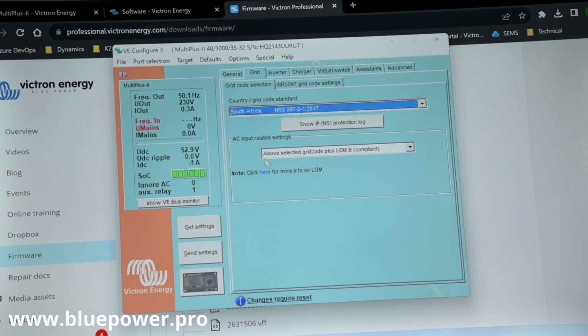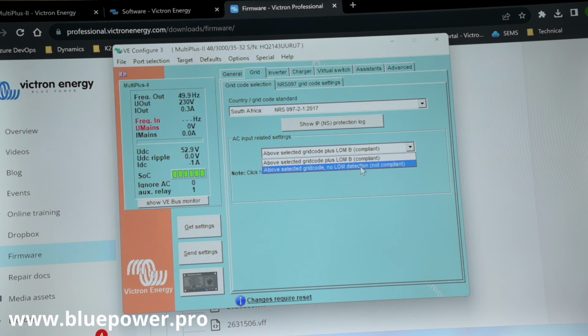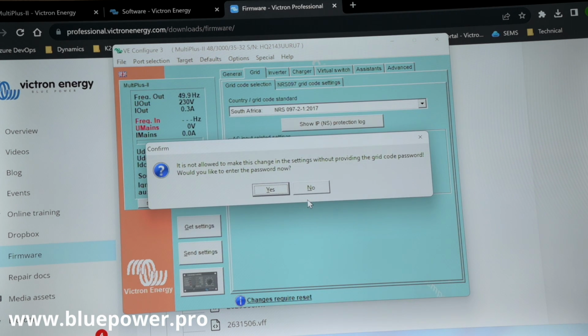But if you've got a generator connected on the input, then it's going to be disconnecting from the generator the whole time, especially if it's a limited generator. Once you start loading the generator, the voltage and frequency drop a little bit, and then the inverter sees it as a failure and disconnects from the generator. It reconnects, initiates the charge, and then disconnects immediately. That's where the LOM detection has to be disabled for a generator. But do note, if you disable the LOM detection, then it's not going to be compliant if you've got grid on that input, so you're not going to be able to get sign-off for the system.